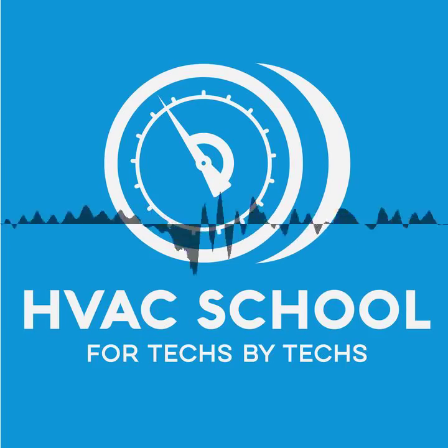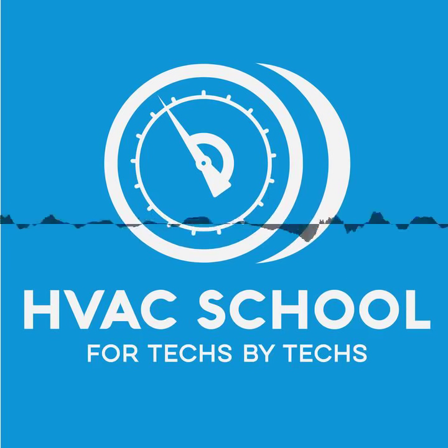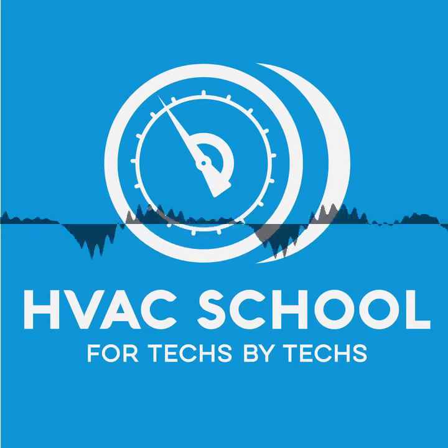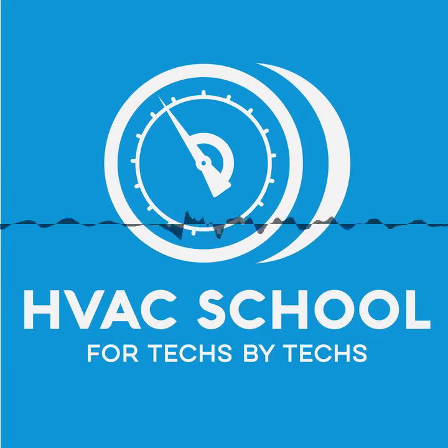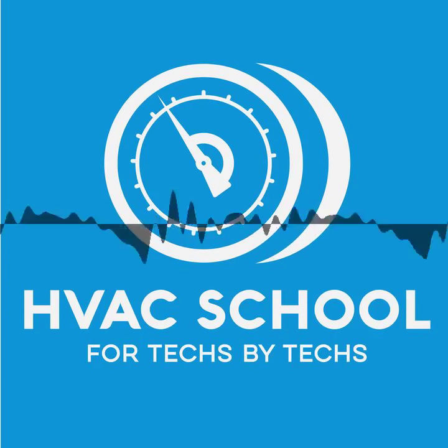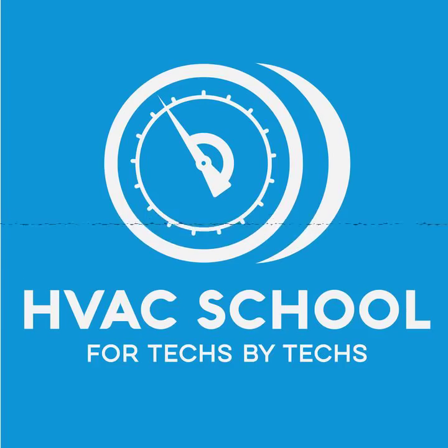And that's why we have crankcase heaters in a lot of cases. Crankcase heaters are what help solve that problem. That's why crankcase heaters become even more important in heat pumps, because we're operating them even when it's really cold outside. So the system goes off, and then we're about to start it up when, let's say, it's 20 degrees outside. Well, the coldest point in that system is the compressor, let alone the fact that refrigerant oil attracts refrigerant anyway. Just by its very nature and the vapor pressure there, it attracts refrigerant into it. Plus, add in the fact that it's the coldest section, it's definitely going to condense liquid refrigerant inside there. So using a crankcase heater helps prevent that. It's probably the easiest way. You can also use a pump down solenoid and some other things.